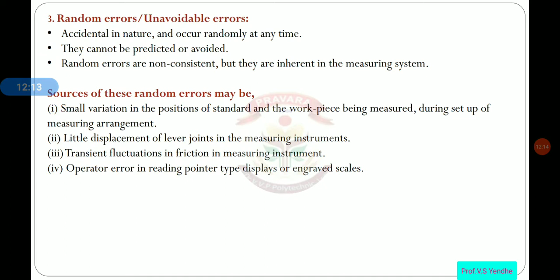Then little displacement of levers or joints in the measuring instrument. If any part like joints, pins, or levers is displaced from its original position and gets settled at another position, in that case there is production of random errors. Then transient fluctuations in the friction in the measuring instruments. Operator error in reading pointer type displays or engraved scales.